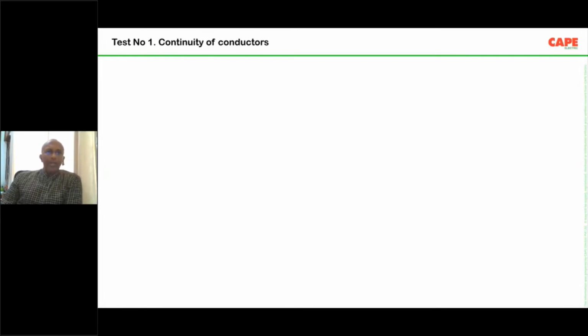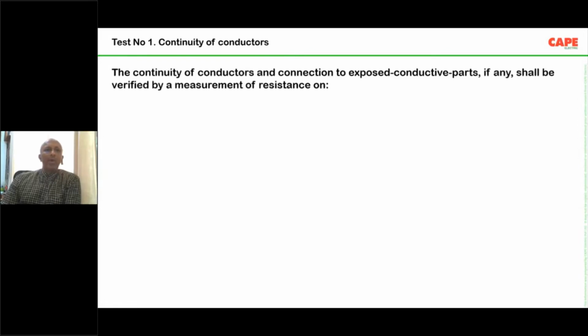In case of a loose contact, what will happen? The resistance of the whole conductor, the resistance of the circuit, will go up. If the circuit is perfect, then the resistance of the circuit is very low. And you must understand that if the resistance is higher, the heat dissipated in the conductor is higher, and after some time it will lead to insulation failure, then a short circuit, then a fire, smoke and other things. So the majority of electrical accidents happen not in the main distribution system, but on the last circuit. The small equipment are the ones creating fire accidents. So the first test is actually highly related to fire accidents, and the test is called continuity of conductors.